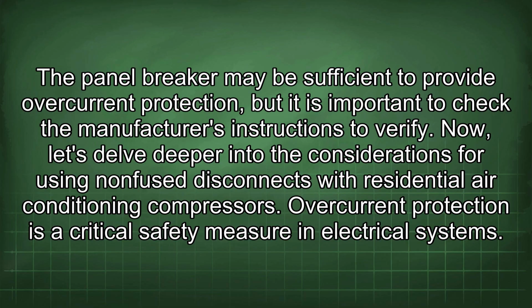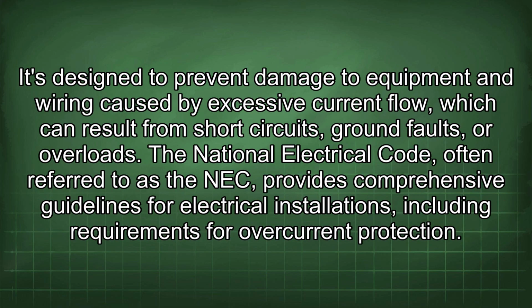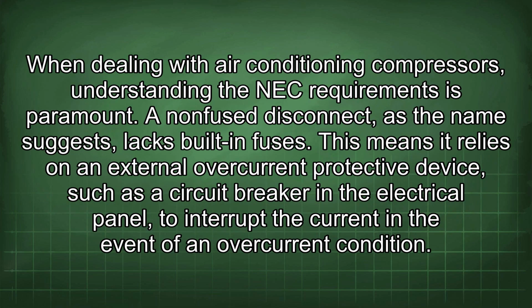Overcurrent protection is a critical safety measure in electrical systems. It's designed to prevent damage to equipment and wiring caused by excessive current flow, which can result from short circuits, ground faults, or overloads. The National Electrical Code, often referred to as the NEC, provides comprehensive guidelines for electrical installations, including requirements for overcurrent protection. When dealing with air conditioning compressors, understanding the NEC requirements is paramount.